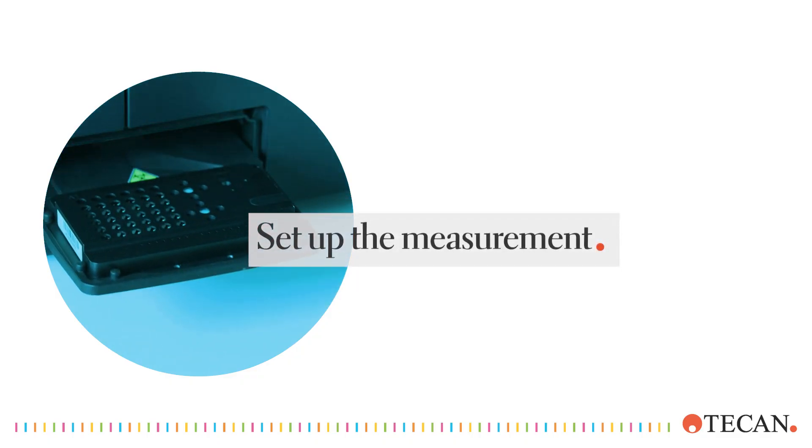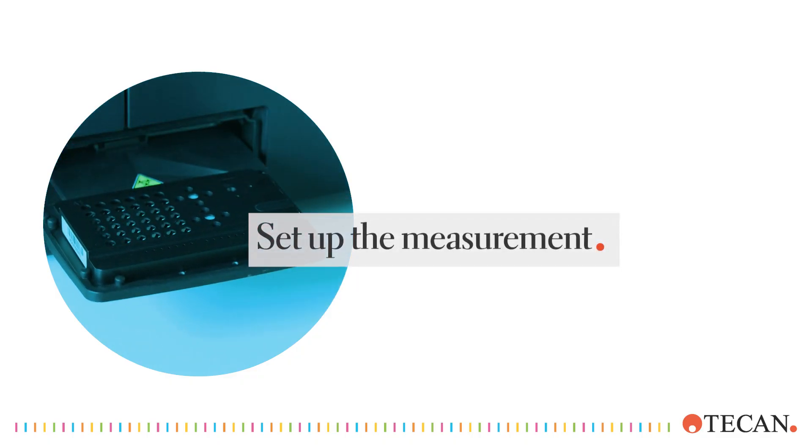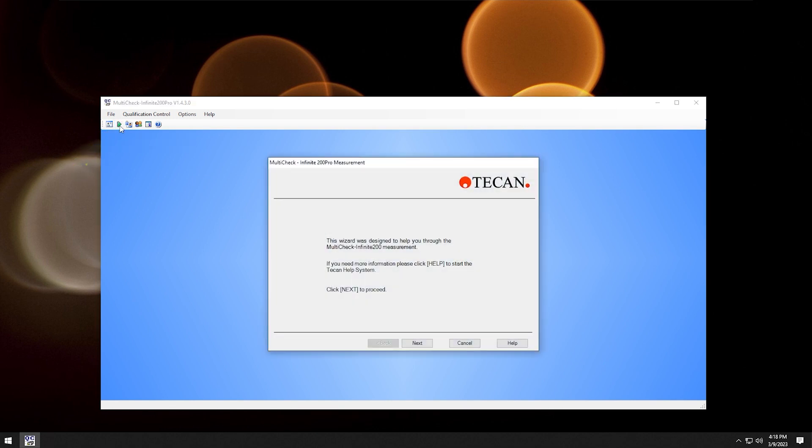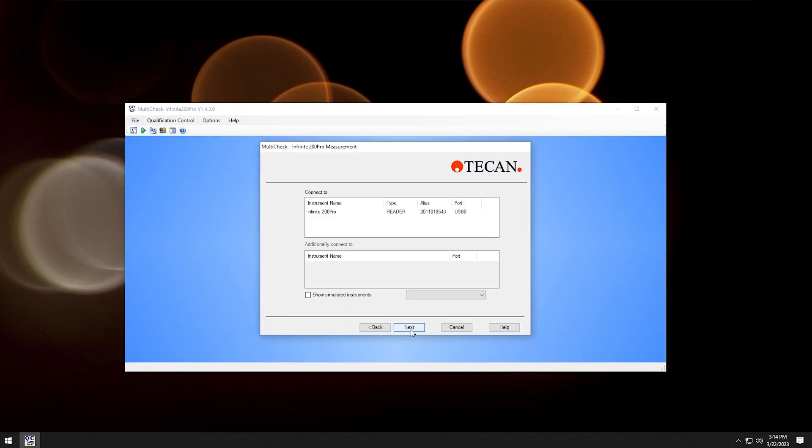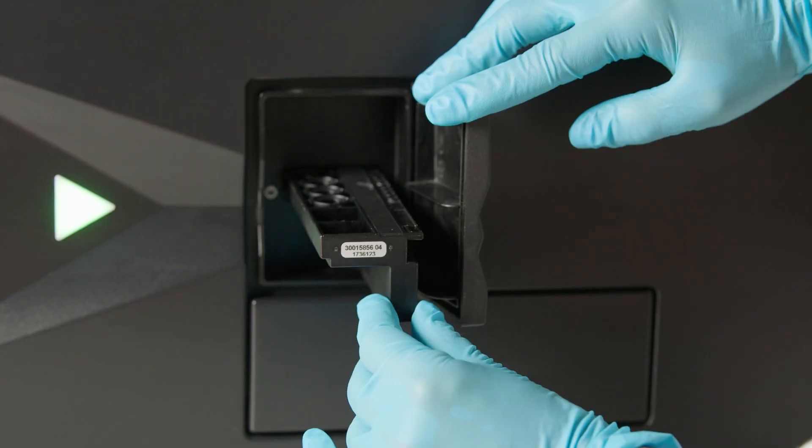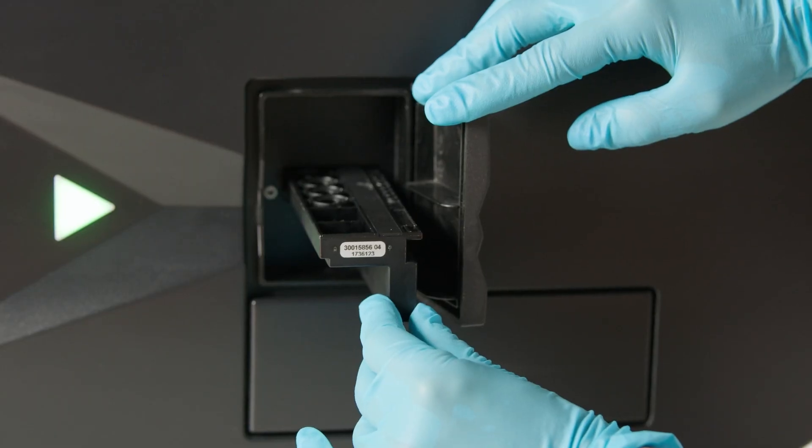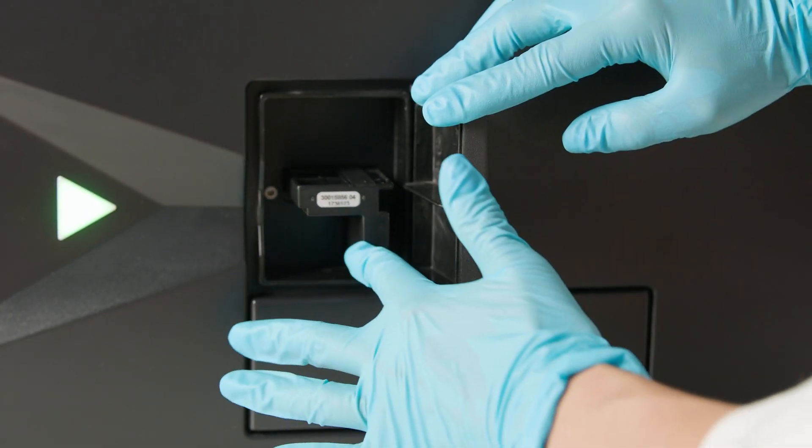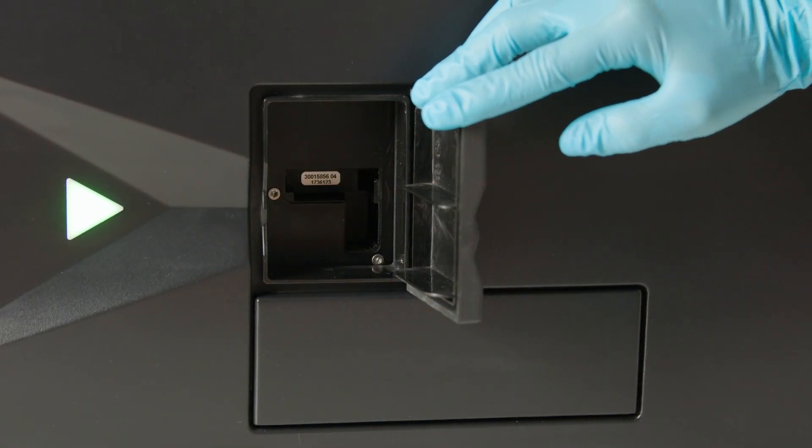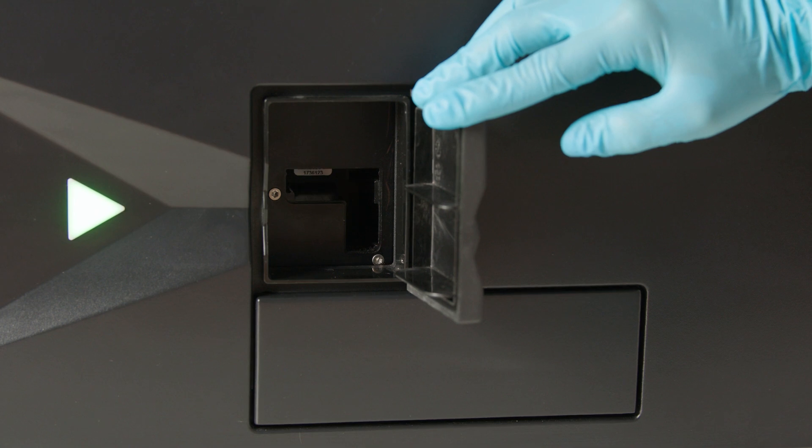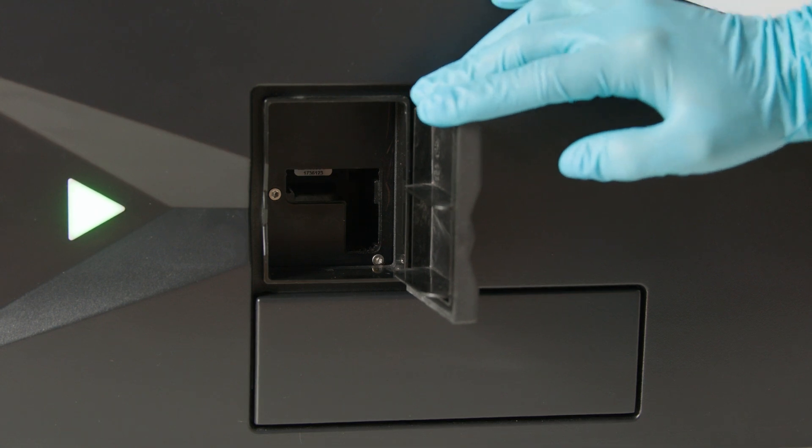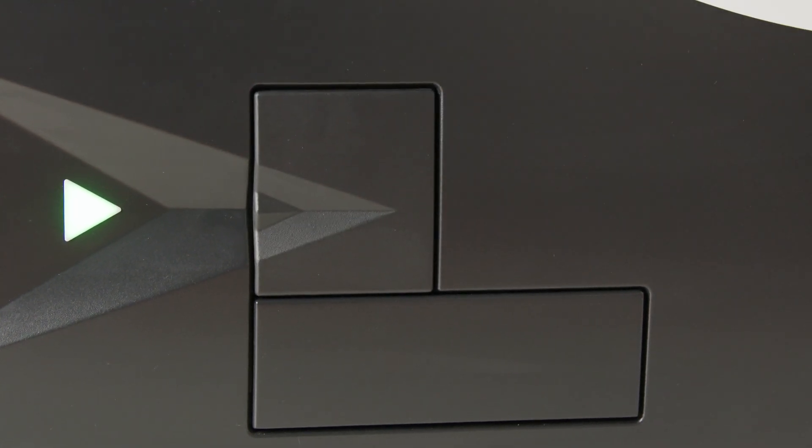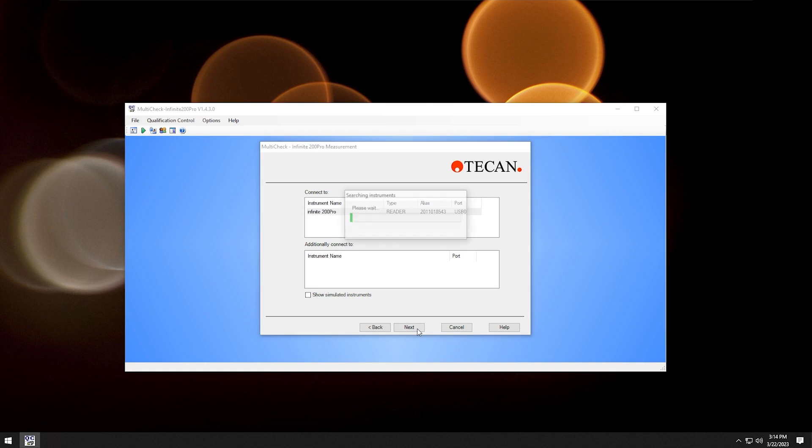Let's set up the measurement. Once the file is uploaded, click on the play button. Click next to proceed. To connect the instrument, click on the specific name, in our case the Infinite 200 Pro. When using a filter-based instrument, make sure to insert the QC filter slide for testing. This is how to insert the filters. Click next.